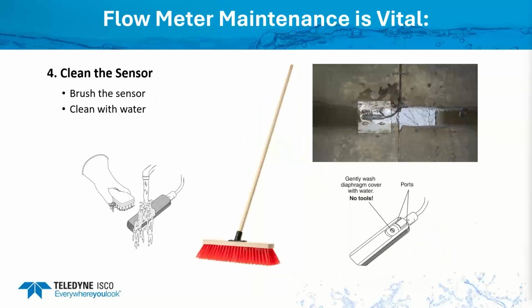Now, as far as cleaning the sensor, what I recommend on an AV sensor is you can remove it and just use tap water. You could use a brush on the top of the sensor, but do not use a brush to clean the actual diaphragm. They're very sensitive. When you're cleaning the actual diaphragm itself, you should just run tap water over it and flush it out to clean any debris out of there.